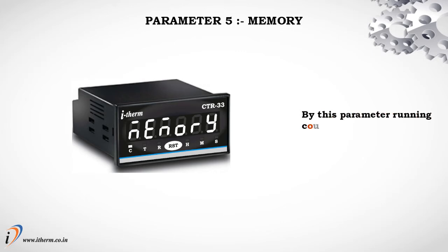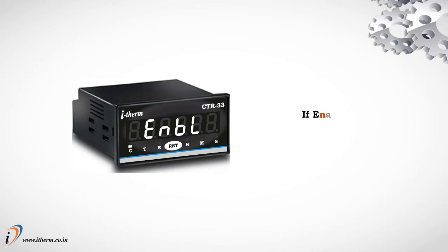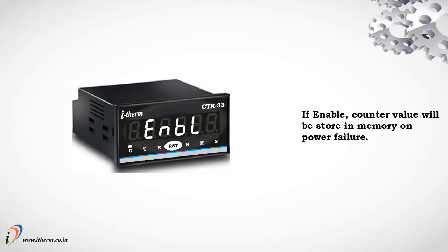Parameter 5: Memory. By this parameter, the running count value can be stored. If disabled, the running count value cannot be stored on power failure, and on the next power on the counter will be reset. If enabled, the counter value will be stored in memory on power failure.